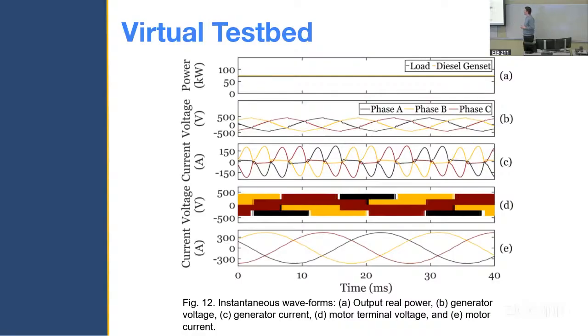But we're inducing some load on top. You see the output from the generator set in waveforms B and C. The current waveform C goes along with D as, within the drive, the inverter shifts between the positive and negative rails of the DC link — you see those spikes in the current supplied to the drive. The final plot, E, is just the 3-phase current being supplied to the motor.